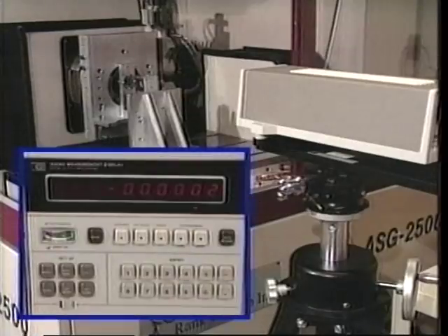The last distance measuring instrument to be discussed in this lab is the linear laser interferometer system. These systems have nearly half microinch resolution, as well as measurement ranges exceeding 100 feet. While not as high as those of capacitance gauges, typical frequency responses of 10 kilohertz are quite adequate for dynamic measurement.